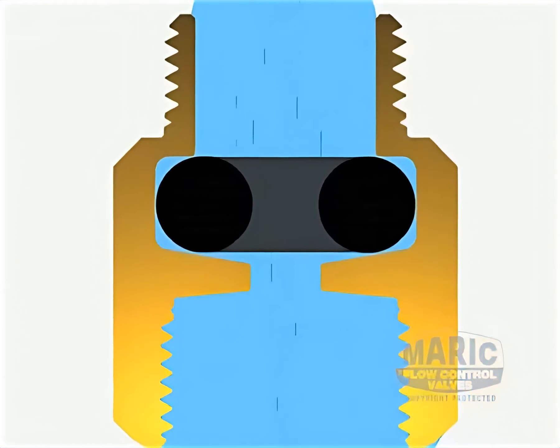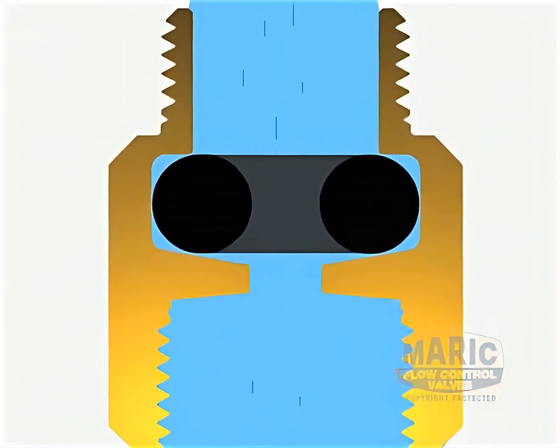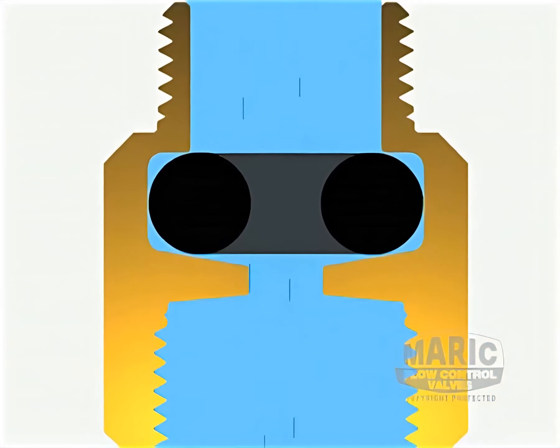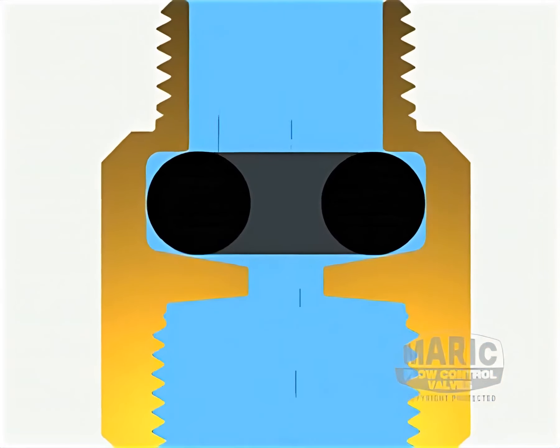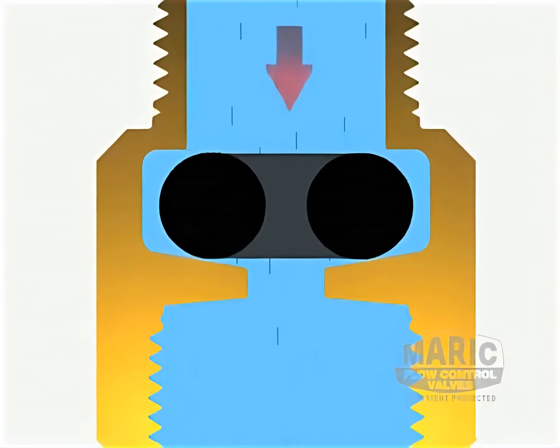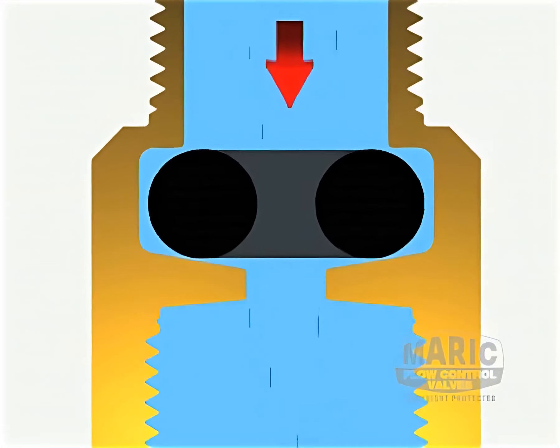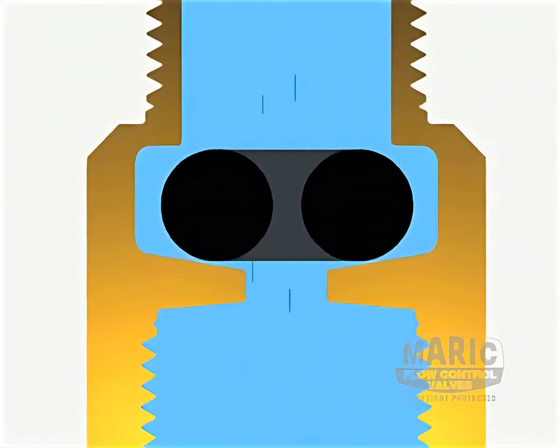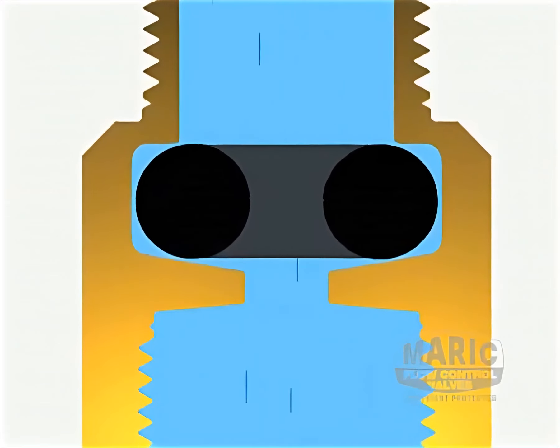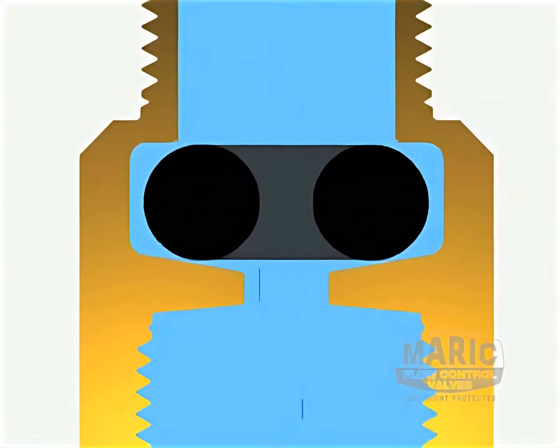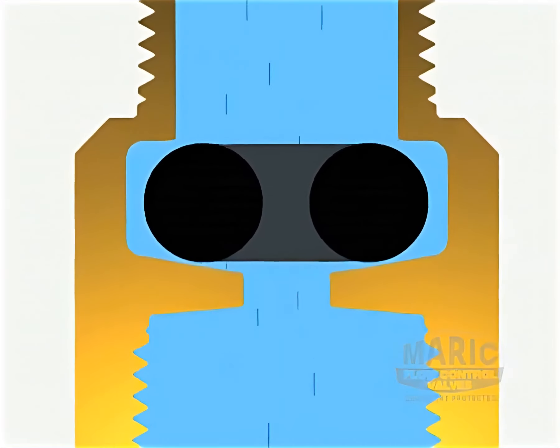These flexible control rings are the heart of the valve. They are manufactured from nitrile butadiene rubber, which is odour-free, taste-free, non-toxic, is unaffected by water or oil and many other liquids, and has a life in excess of ten years under normal operating conditions.